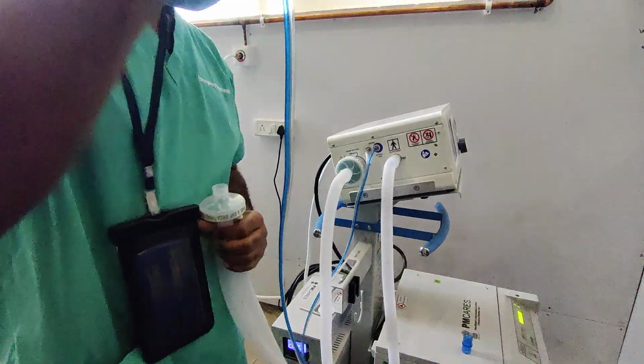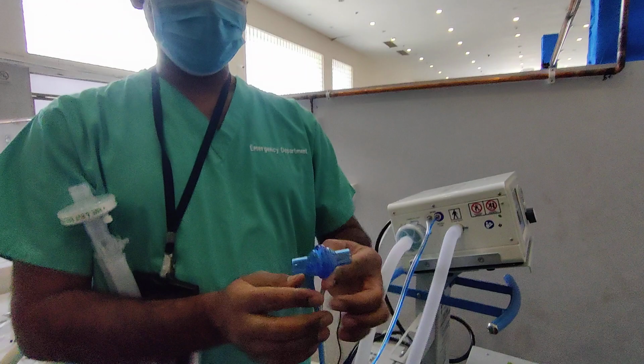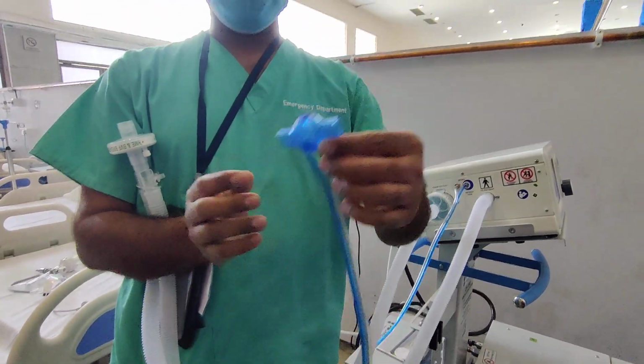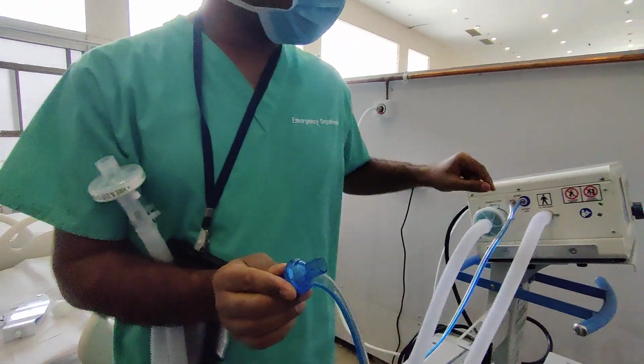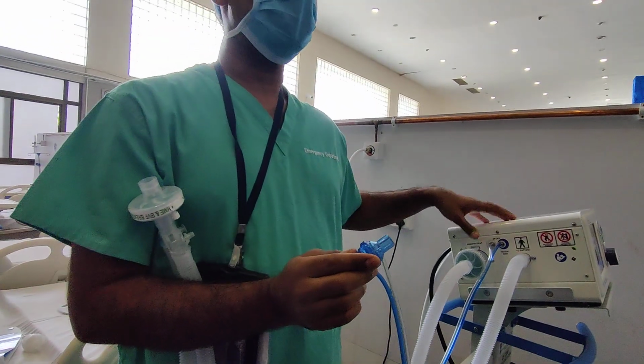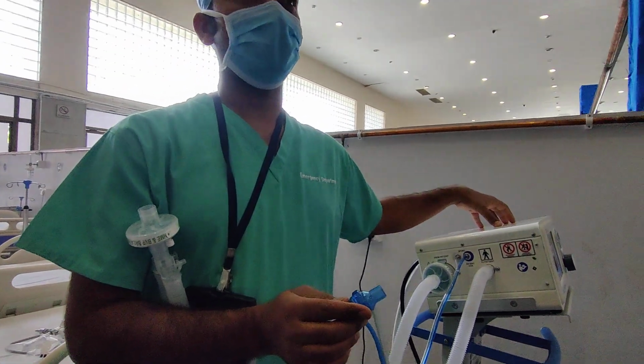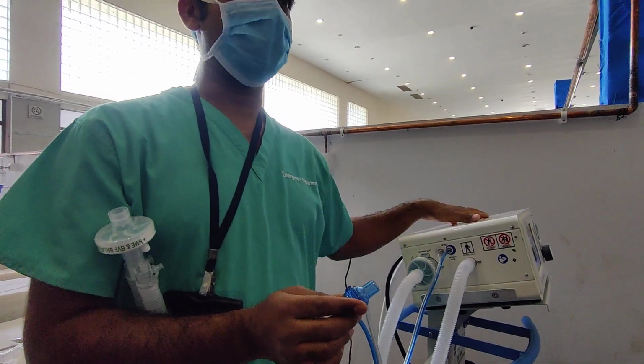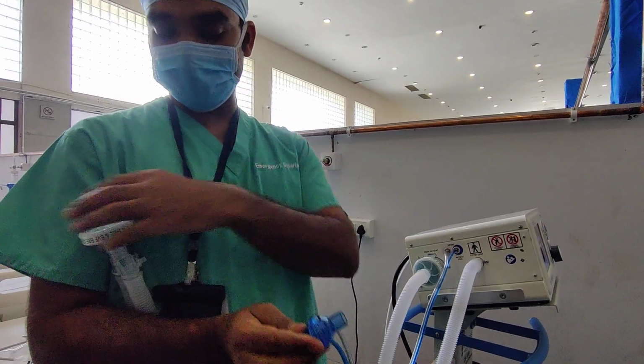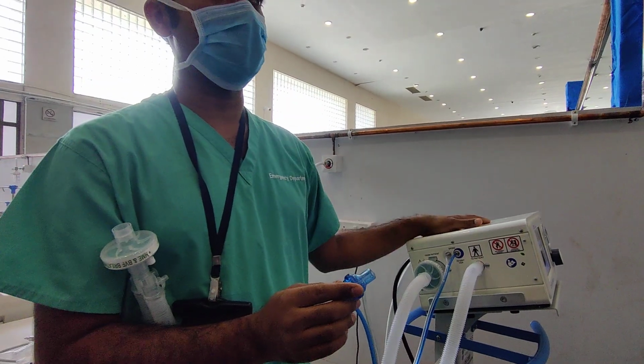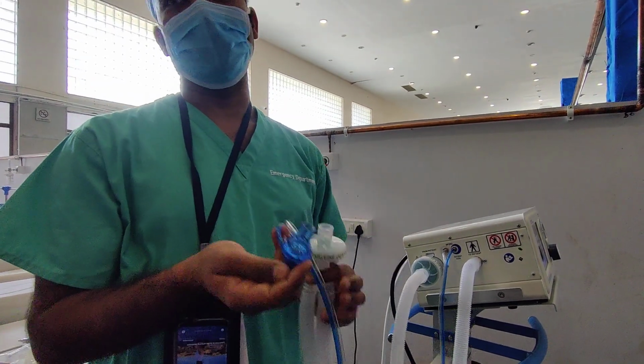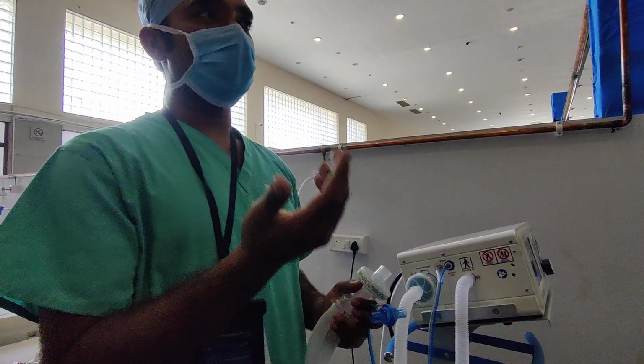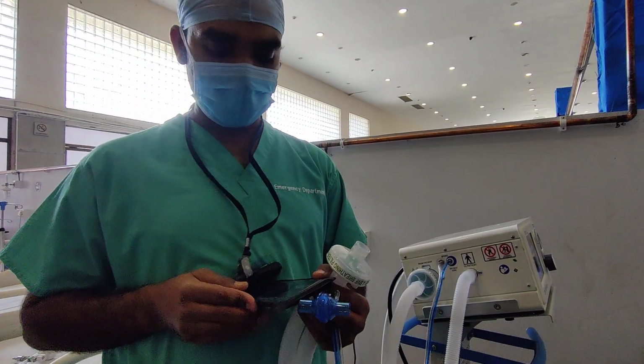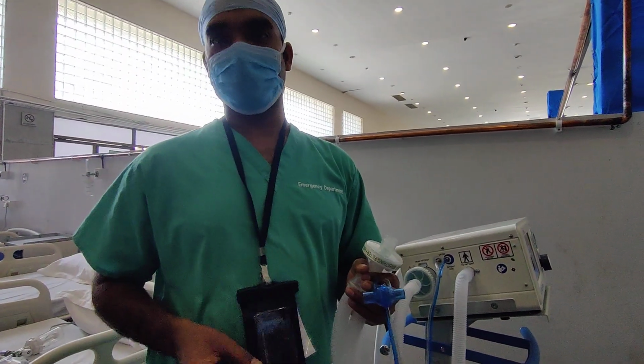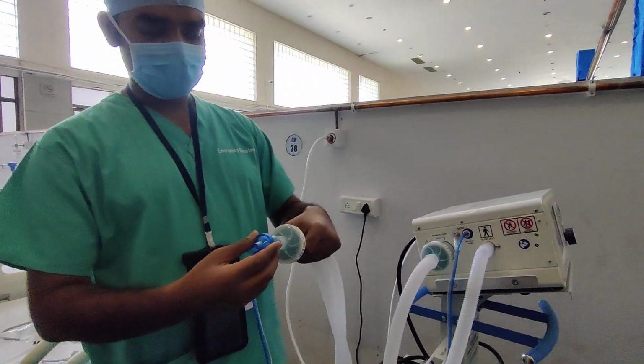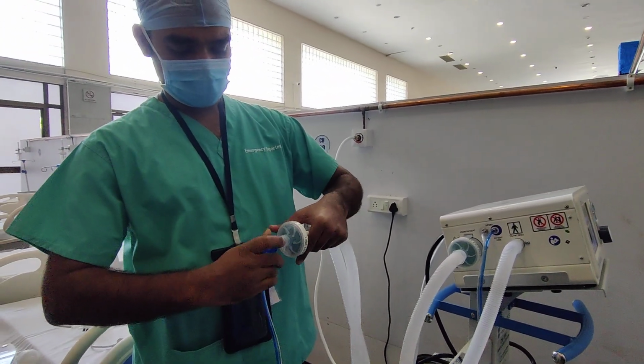So once this filter is applied, you need to connect sensors here. These are the sample tubing. So what this sensor does, inspired and expired air goes from these sample tubings into the ventilator, and the machine will give you values: how much inspiratory volume was there, how much expiratory volume was there, what was the pressure inside the circuit. So machine will give you all the values. If you don't connect this sensor, you won't get any values. So you will not know how your patient is doing. So connect this sensor on this filter here.